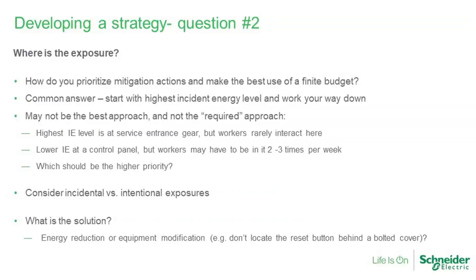And so, again, the first step: define a set of safety-related performance requirements. The second one: look at where the exposure is. We've talked about this a little bit already, but how do you prioritize mitigation actions and make the best use of a finite budget, which we know it always is, right? One of the common answers: start with the highest incident energy level and work your way down. We talked already about what if your workers are into MCCs or control panels on a regular basis, doing troubleshooting or whatever. Even if the incident energy levels are lower, their exposure is higher, and it may make sense to look at solutions for those locations first, rather than simply starting with the high energy locations where you don't have much interaction.